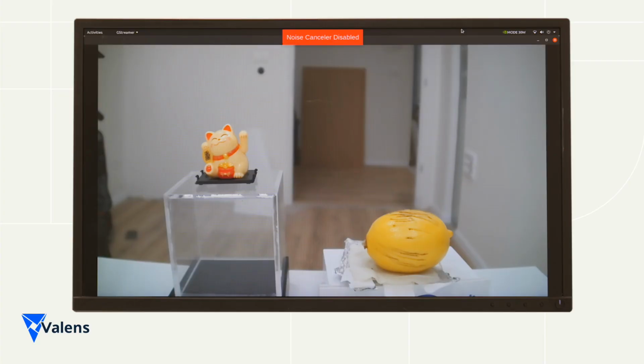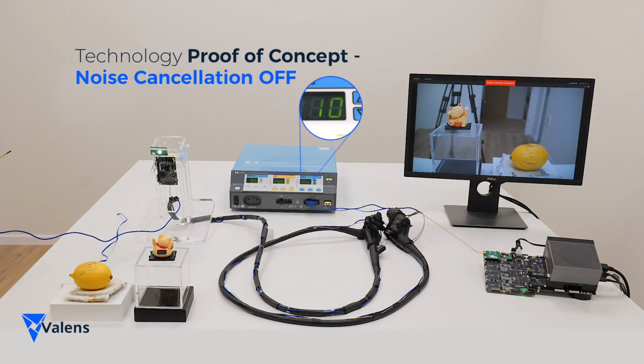Solutions on the market today using only forward error correction or no correction methods at all cannot handle the electrosurgical procedure interference. We simulate this by running the setup with the VA7000 noise canceller disabled. Turning on the noise generator to a level of just 10 watts and using the probe on a lemon simulating a patient, the link fails and the video freezes.